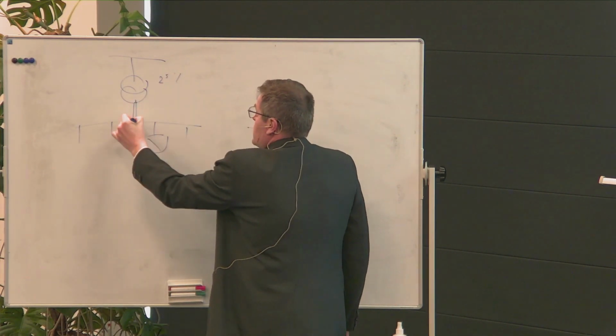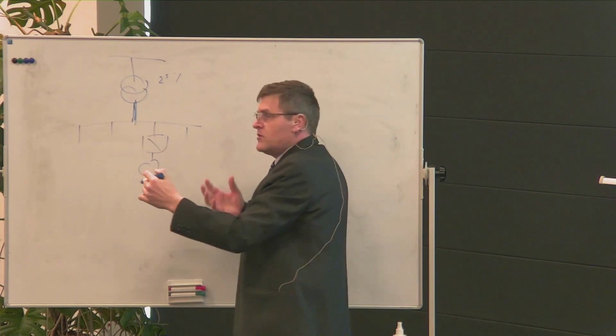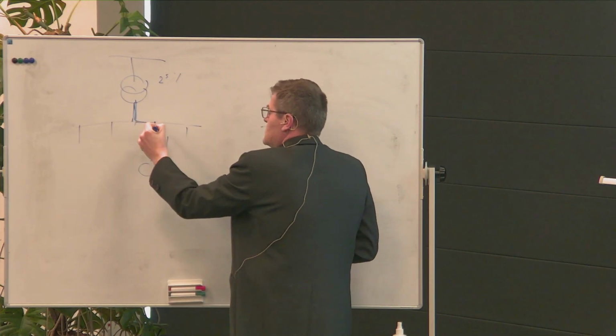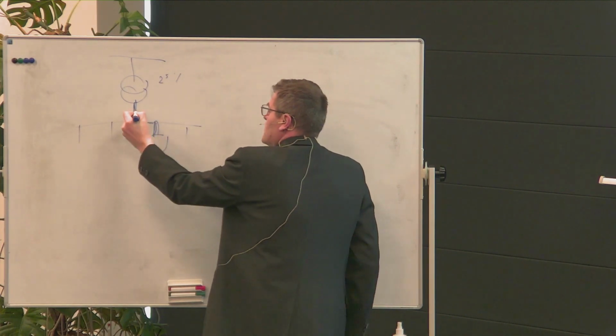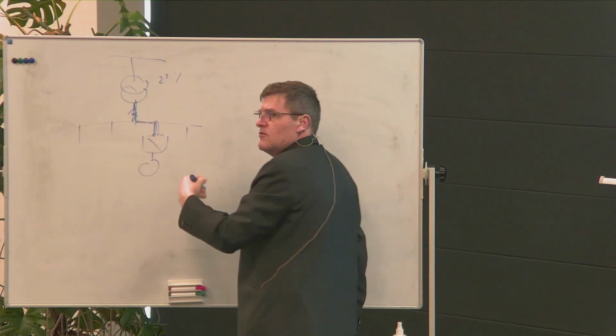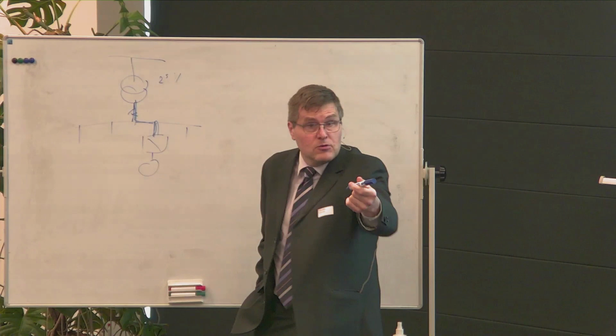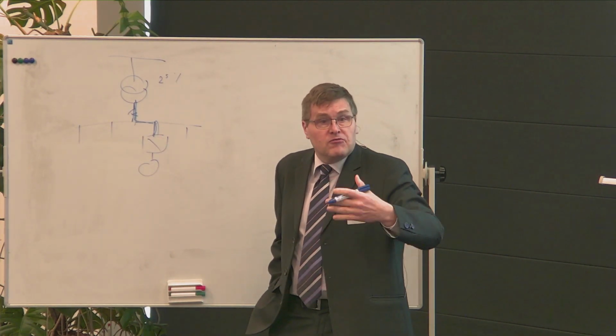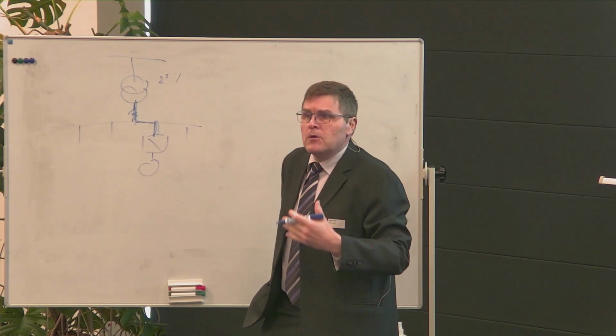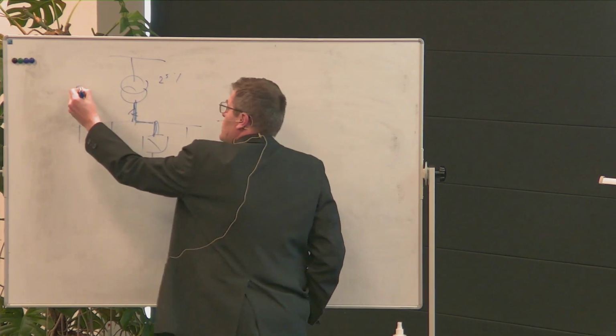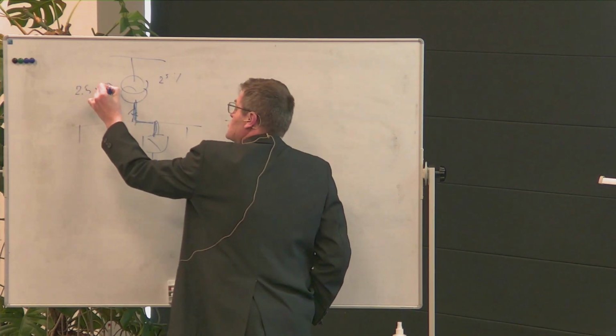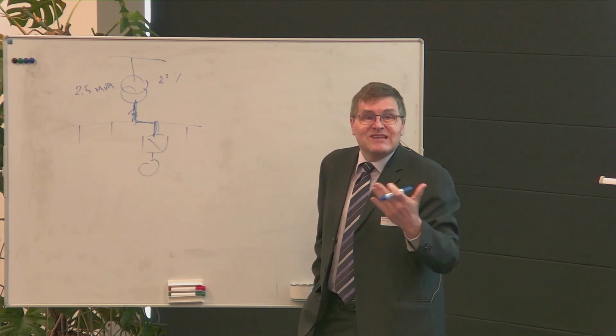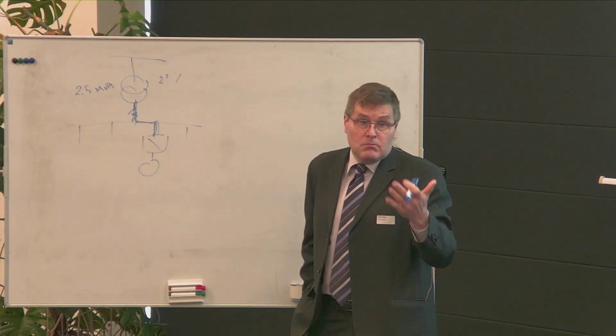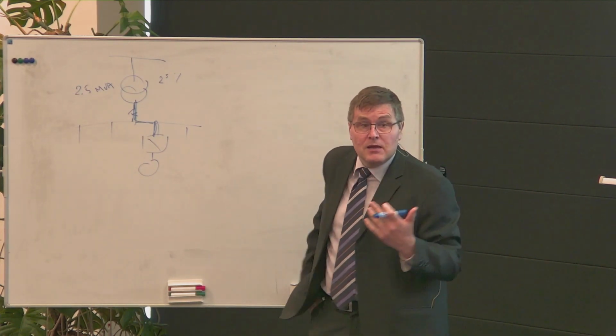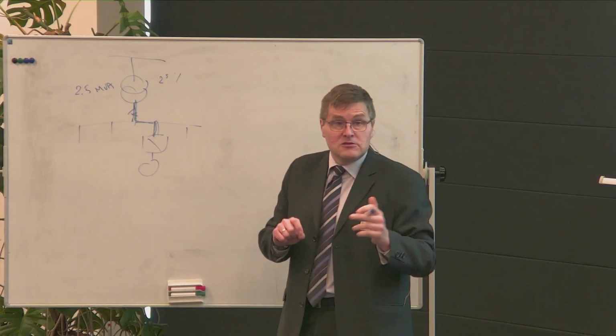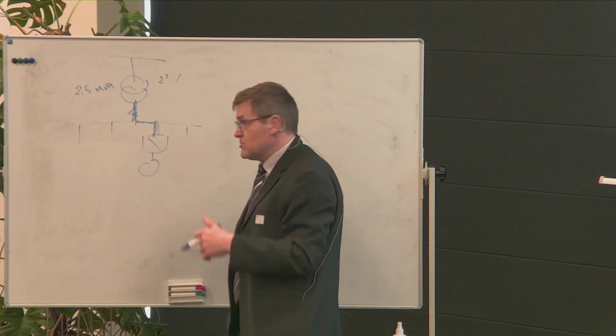You have a bus bar here, a very strong bus bar. You have a distribution line, switchboard, breaker here. Few percent losses. You mentioned that there is a lot of heat produced, but when you have a 2.5 MVA transformer, if you have 1 kilowatt of heat, it could burn your cable. With 1 kilowatt out of 2.5 megawatts, it's 0.04%. So you don't see that.